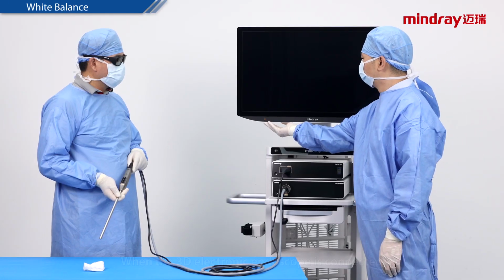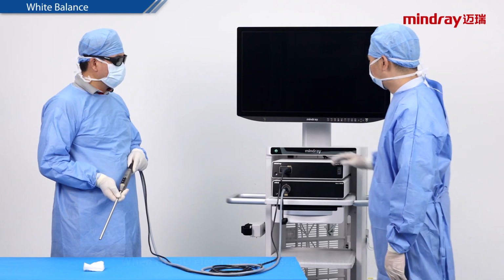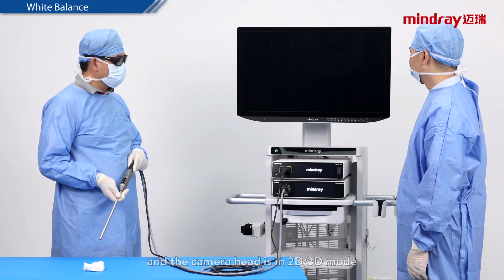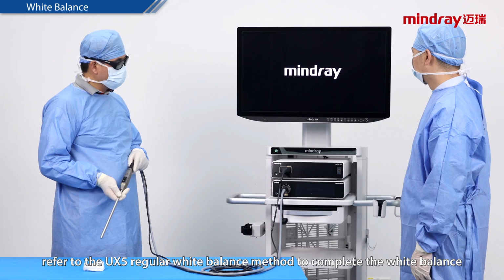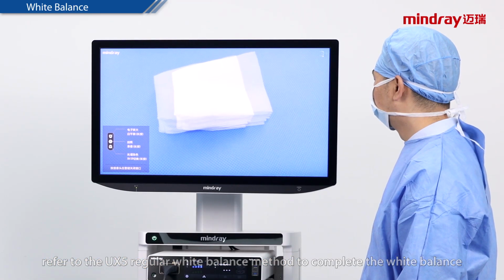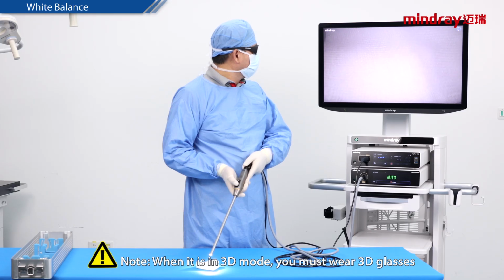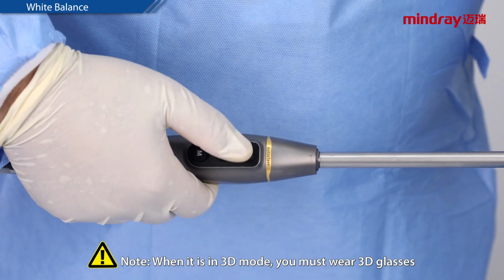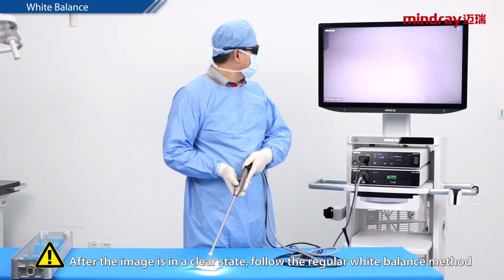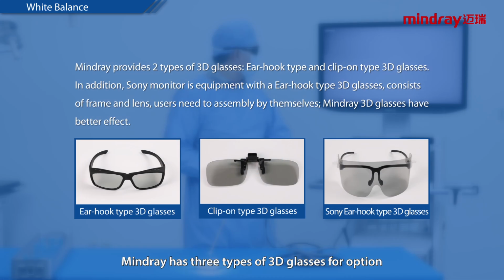White balance. When the 3D electronic endoscope is connected and the camera head is in 2D 3D mode, refer to the UX5 regular white balance method to complete the white balance. Note: when it is in 3D mode, you must wear 3D glasses. After the image is in a clear state, follow the regular white balance method. Mindray has 3 types of 3D glasses for option. 3D glasses equipped with 3D monitor. 2 types glasses equipped with UX5 video camera system, earhook type and clip-on type.